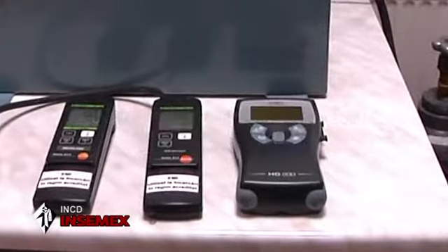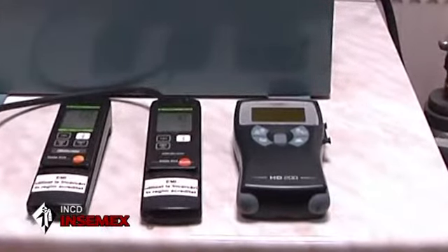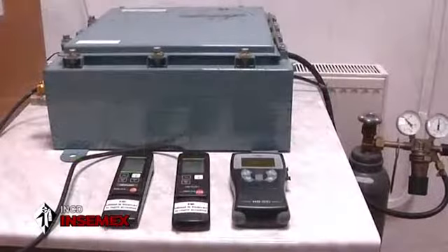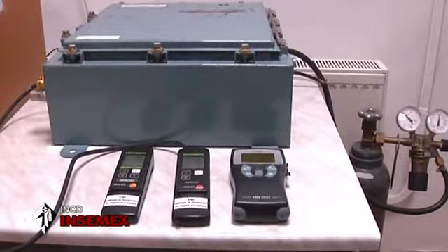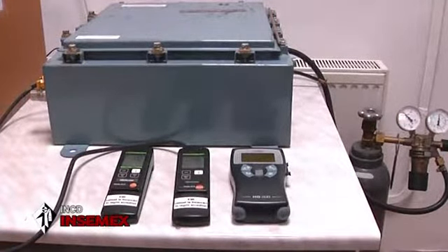Stand for testing equipment with pressurization type of protection. The stand for testing equipment with pressurization type of protection comprises the following: an installation which transfers the testing gas within the pressurized enclosure to be tested, helium and carbon dioxide bottles as appropriate.